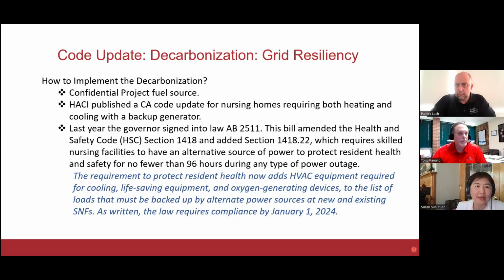In 2020, commercial buildings consumed 18% of the energy in the US. 35% of the overall consumption is electricity. The state of California is a leading state implementing energy standards. However, HACI also published a code update, which requires both heating and cooling system in nursing homes backed up by an alternative source of power with 96 hours of operation. Next slide, please.